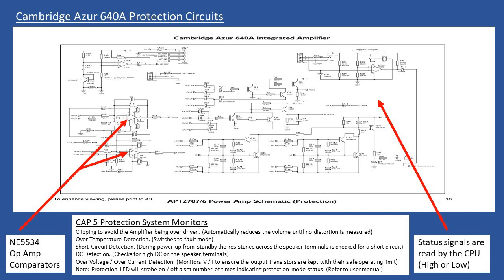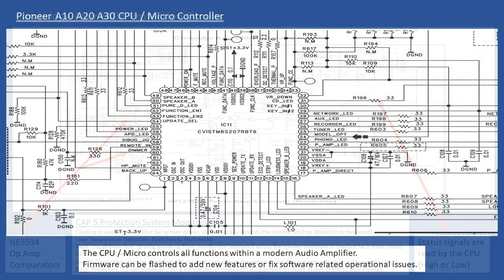This brown glue in the protection circuits causes a lot of issues, and it always causes issues with intermittent operation. It could be that randomly the over voltage protection seems to be operating and there is no excessive DC voltage on the back of the terminals, so why is it operating? You'll see on many of the videos I show you internally, you can see this brown glue is in there, and what has happened is it's formed a conductive path between parts of the circuit where it should not have been. And that's why the fault protection system is operating, because all of a sudden the inputs to the comparators or maybe the detection transistor circuits are randomly sensing an input voltage which shouldn't be there, and then that signal is flipping, turning on logic 1, and is then read by the microprocessor. So just be aware of that.